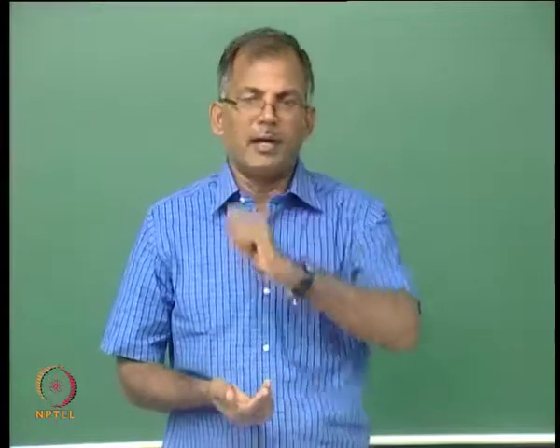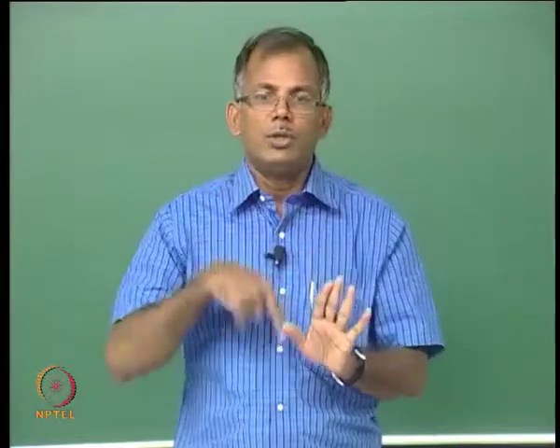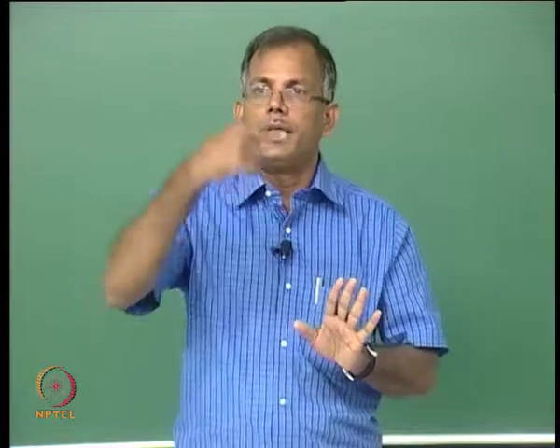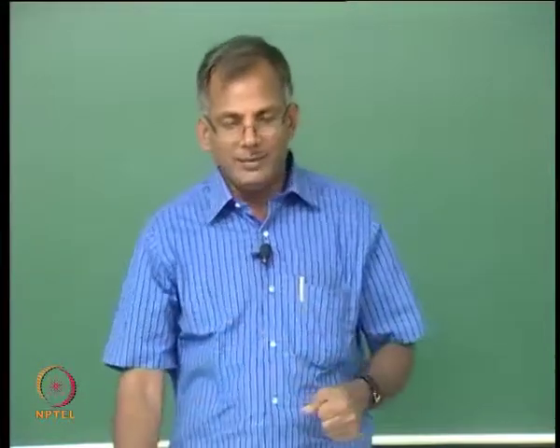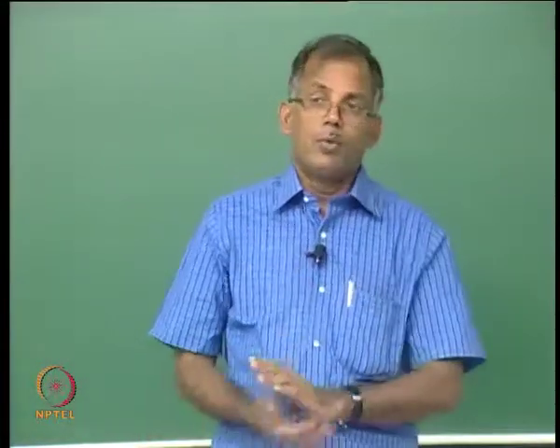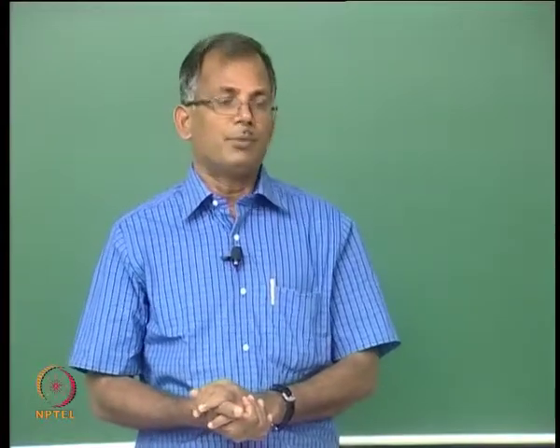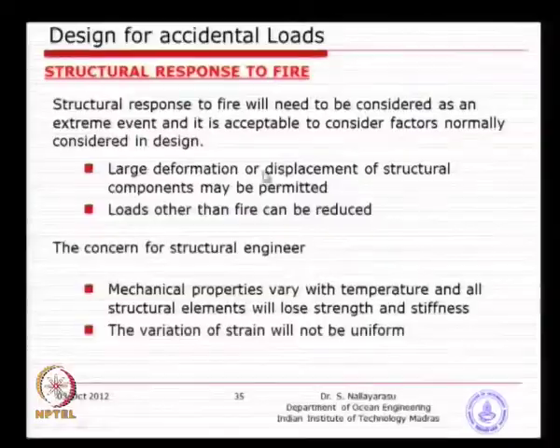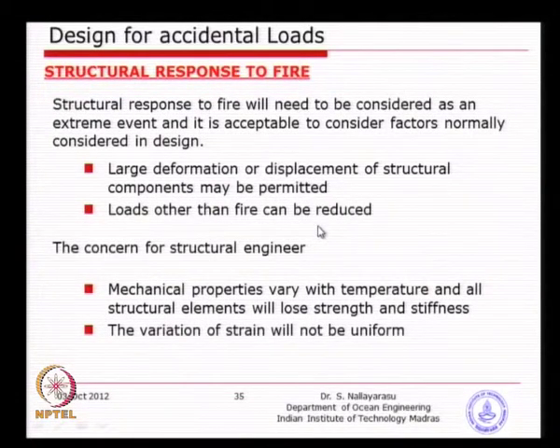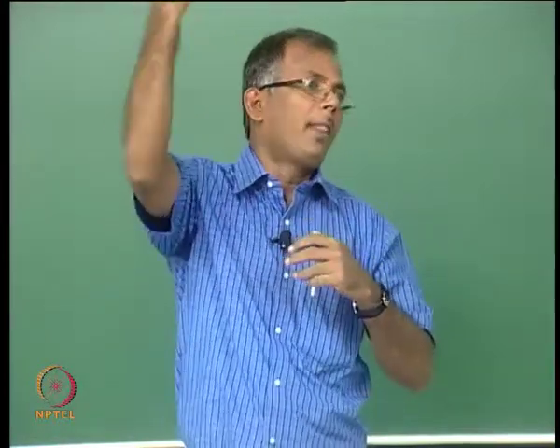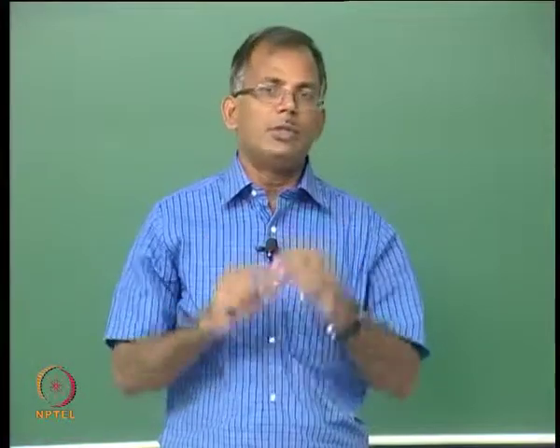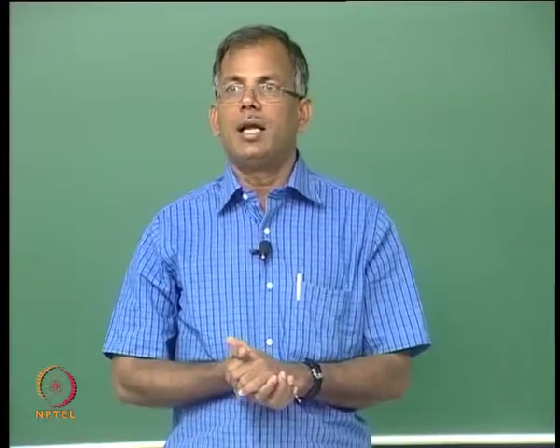For example, if a piece of equipment is half a meter away and the blast wall deforms and hits that equipment, it creates a chain reaction of subsequent fire and blast. Deformation is permitted provided it is not harmful to subsequent events. You also need a connection detail that can transfer loads from wall to beam, but not from beam to wall, so the wall does not carry other forms of loading.